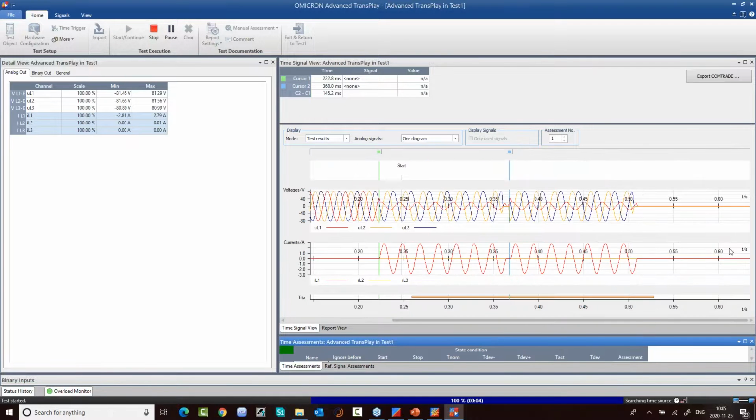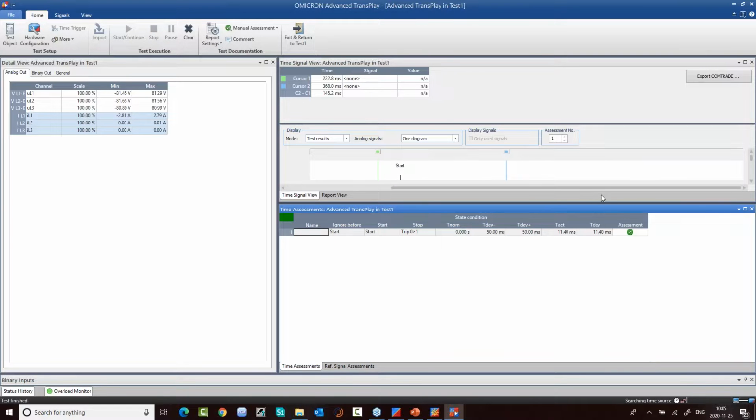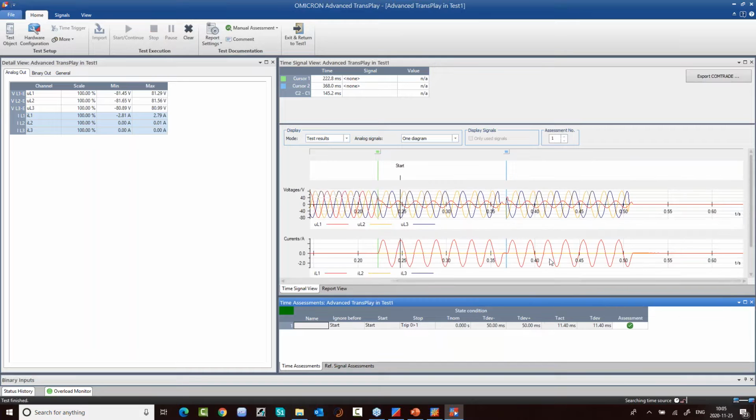It will inject the full wave, and for sure it doesn't affect it because I got the trip very early, because line differential is active. This is another technique of inserting the repetition to extend the fault duration.